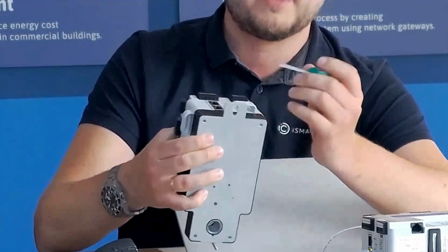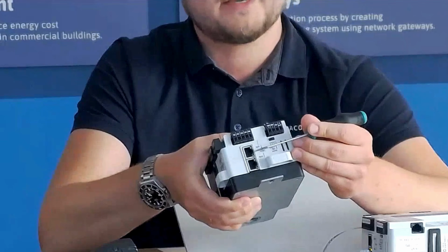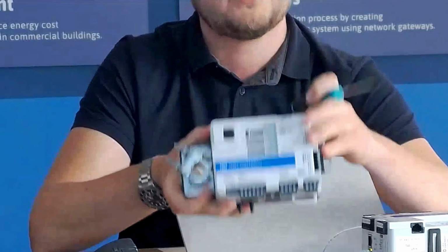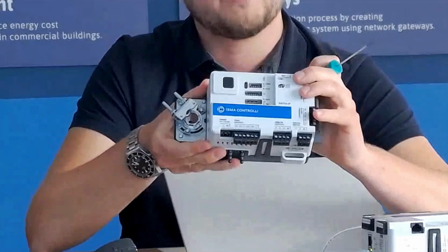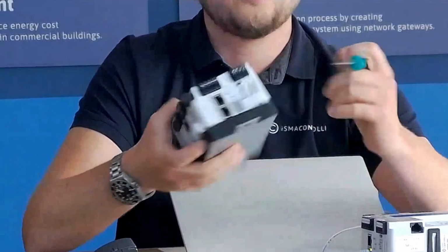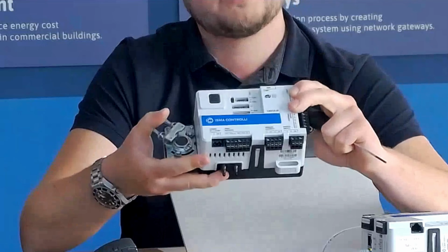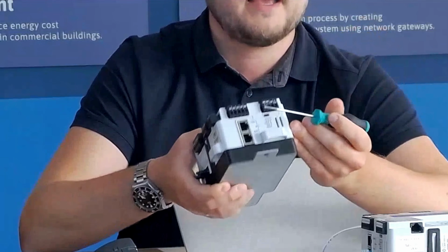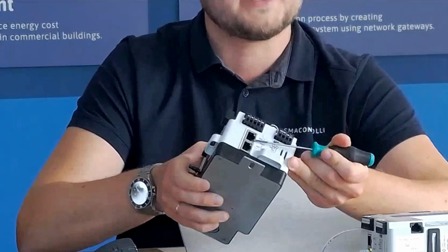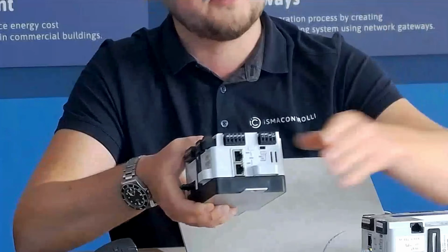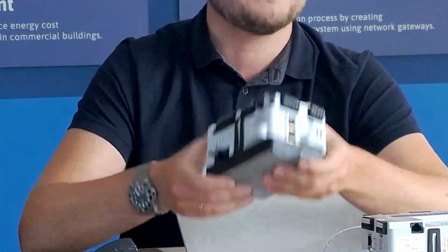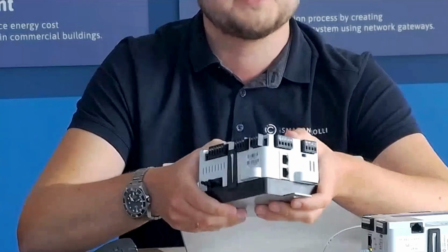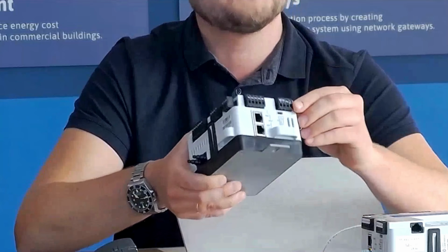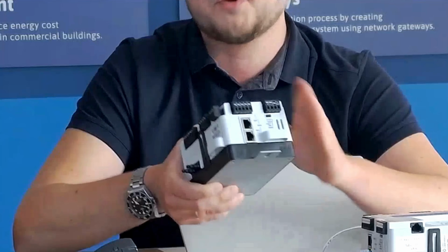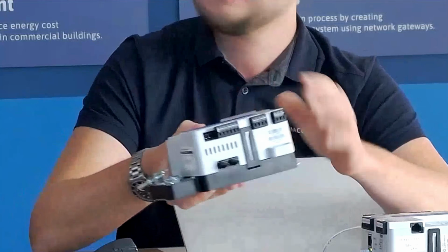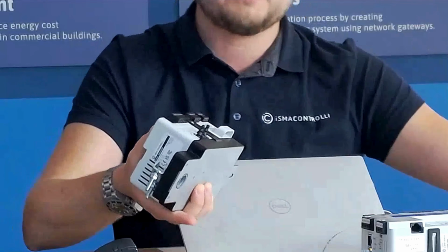So back to the Ethernet ports. You can easily daisy chain all of your VAV units, and you don't need to bring more expensive switches and wire those VAV units one by one on the network. You can simply daisy chain them, and because the fail-safe uses physical switches installed on the board in the controller, even if one of the controllers on the network fails or is disconnected from the network, the communication on the IP will pass through even without power on the unit itself. That's the power of the daisy chain and fail-safe mechanism. Yeah, it's a great feature for daisy chaining.